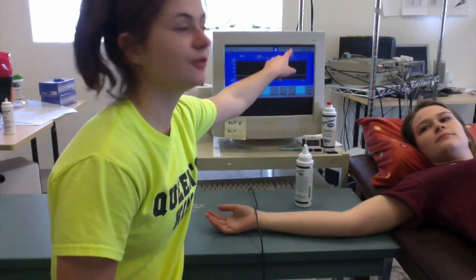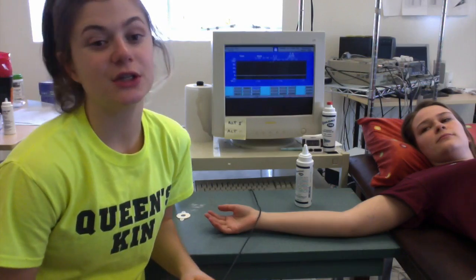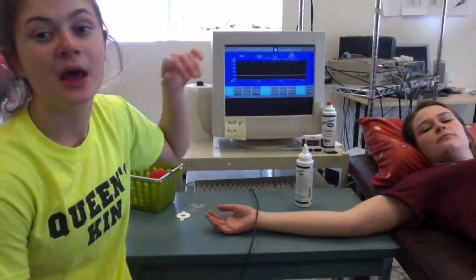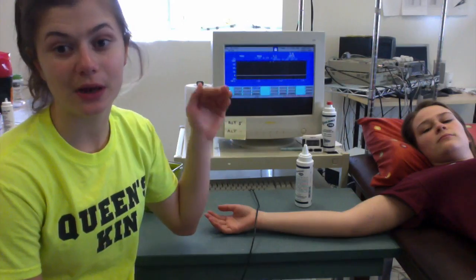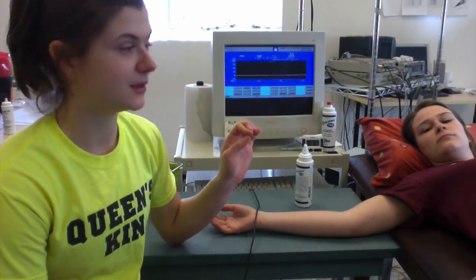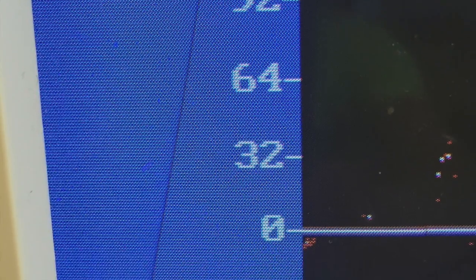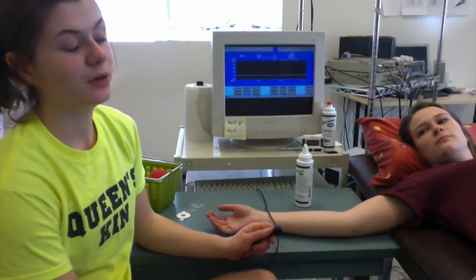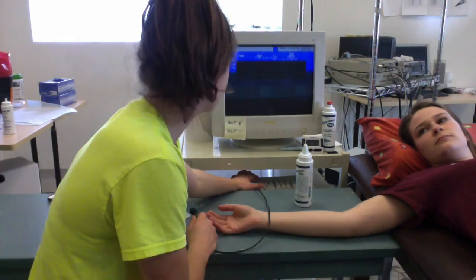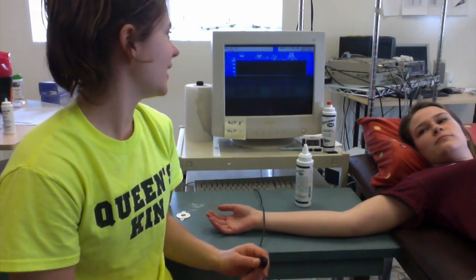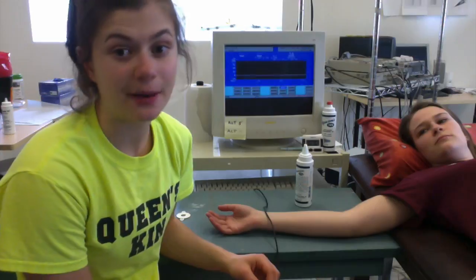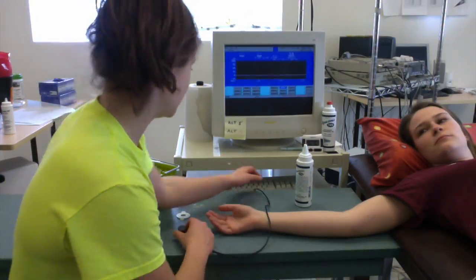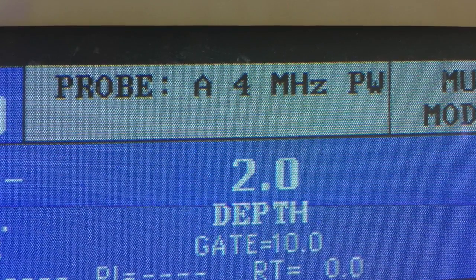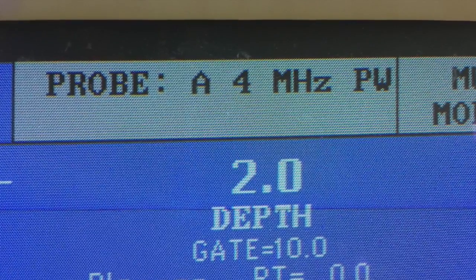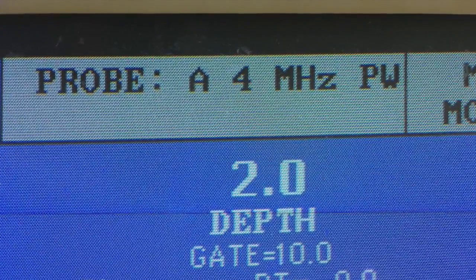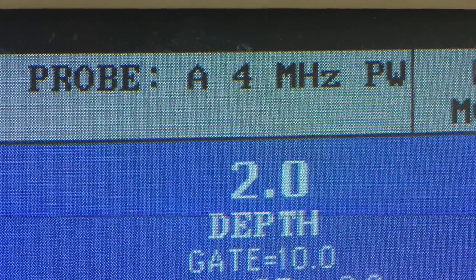Once we have changed the probe to 4 megahertz, we then want to change the scale by changing the offset to be negative 32 at the bottom and 128 at the top, allowing the graph to run through 0. We then want to change the gate to 10 millimeters. Once the gate has been changed to 10 millimeters, we want to change the depth to 2 centimeters. Changing the depth changes how deep the signal goes into the tissue, while changing the gate changes the window of sensitivity that the probe has for picking up a signal.